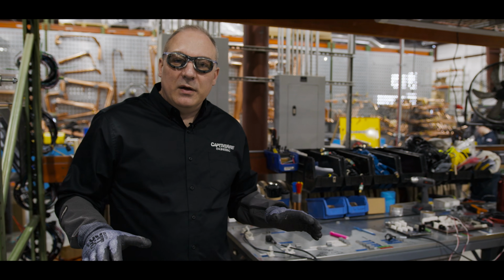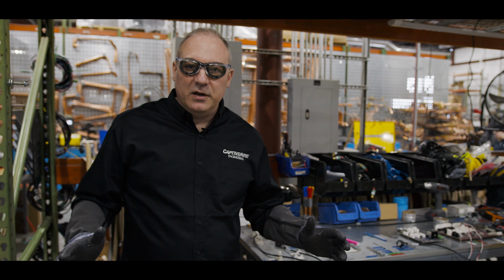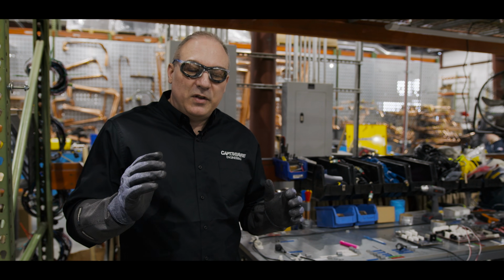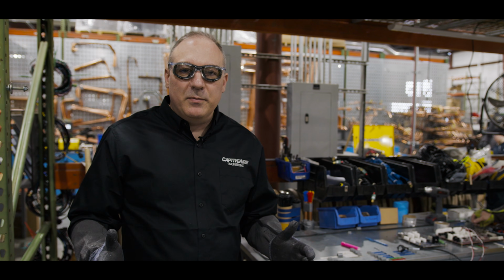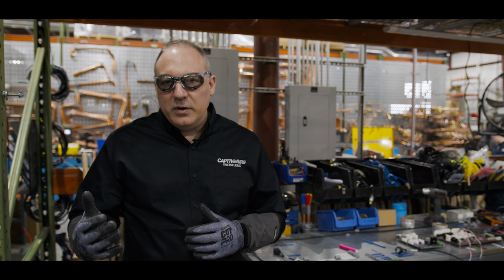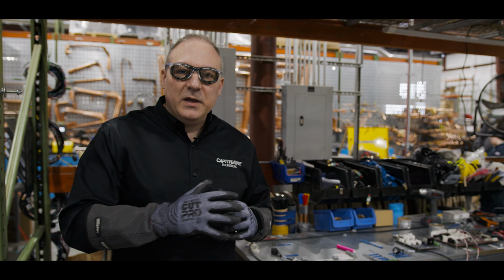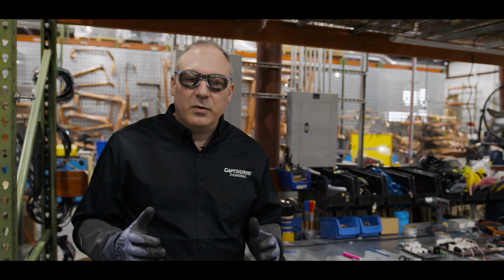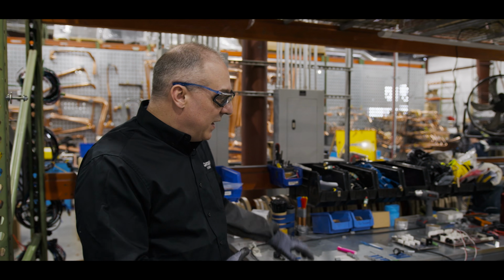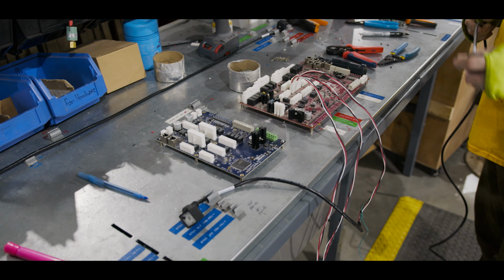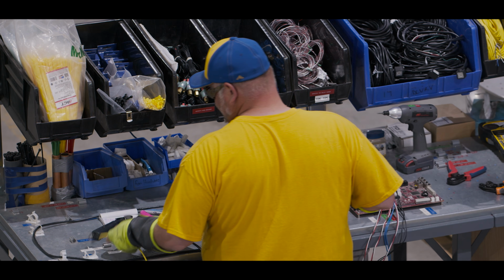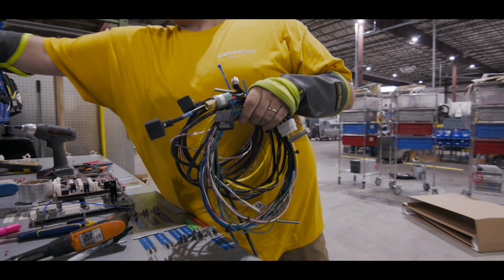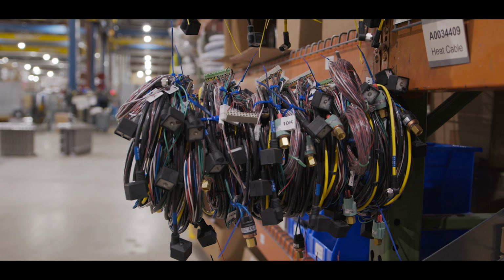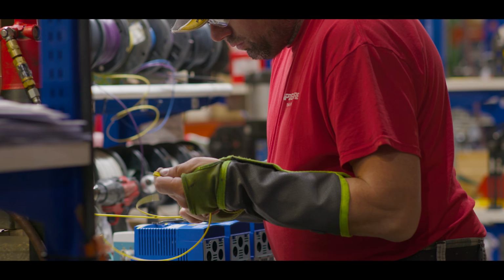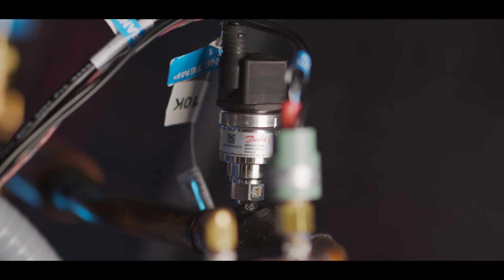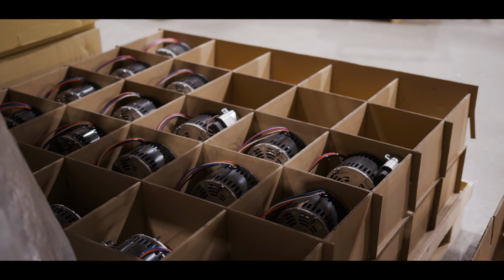Wire routing was variable between all of our facilities, so we wanted to standardize it so that if there was a problem in the field, like an electrical interference issue, we'd be consistent and know where it originated and how to solve it. This template allows production to lay out the components on a board and make sure the wire routing is correct to every component - wires, circuit breakers, sensors, coils, compressors, motors, you name it.